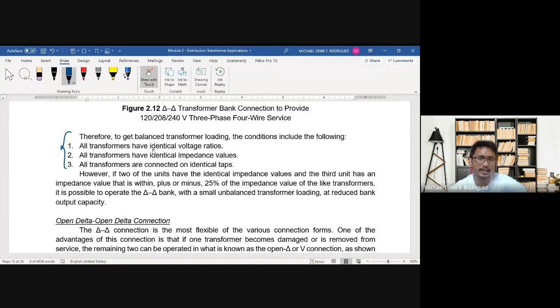If sakali two are identical but one is not, as long as it's within plus or minus 25% of the impedance value, it's still okay for a delta-to-delta bank. But you'll have a small unbalanced transformer loading, and the output capacity of the bank is also reduced. So that's about delta-to-delta.